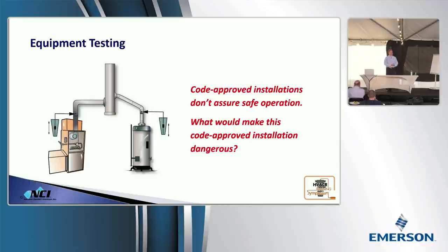While that's happening, that water heater is filling with flue gases. Now, we talked earlier about the combustion byproducts. Carbon dioxide is one of those combustion byproducts. Carbon dioxide is heavier than air. If it doesn't leave the equipment, it backs up inside the heat exchanger. That's where you start to see the CO starting to rise. Because if the flue gases can't get out, guess what can't get in? Combustion air. So the whole time you're seeing combustion air being displaced because of the impact of that inducer.